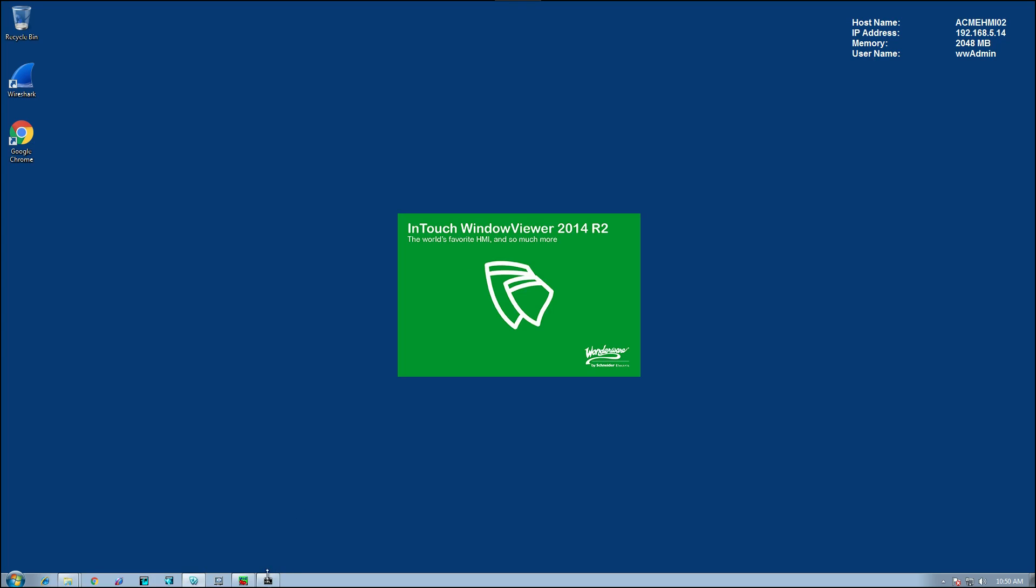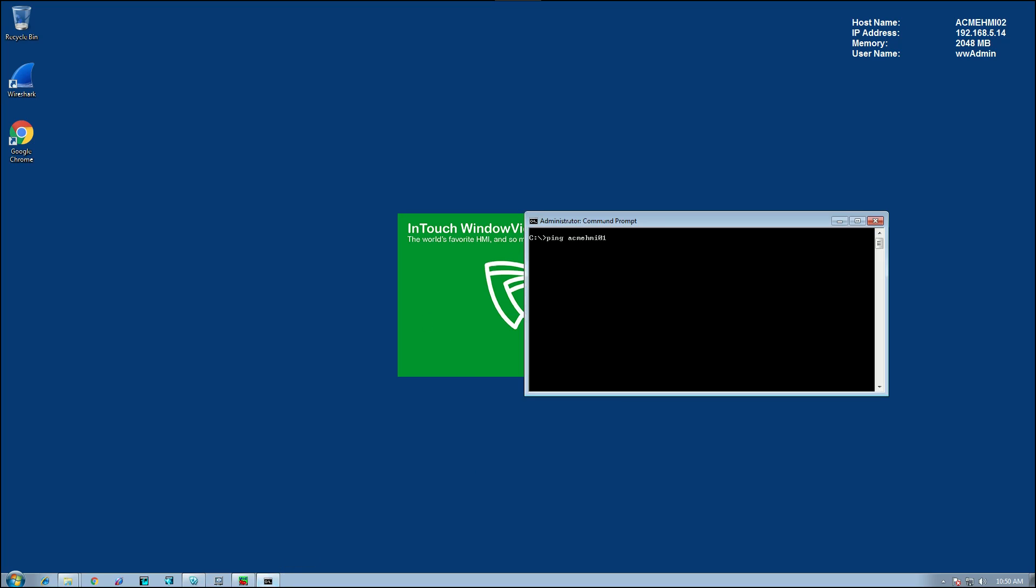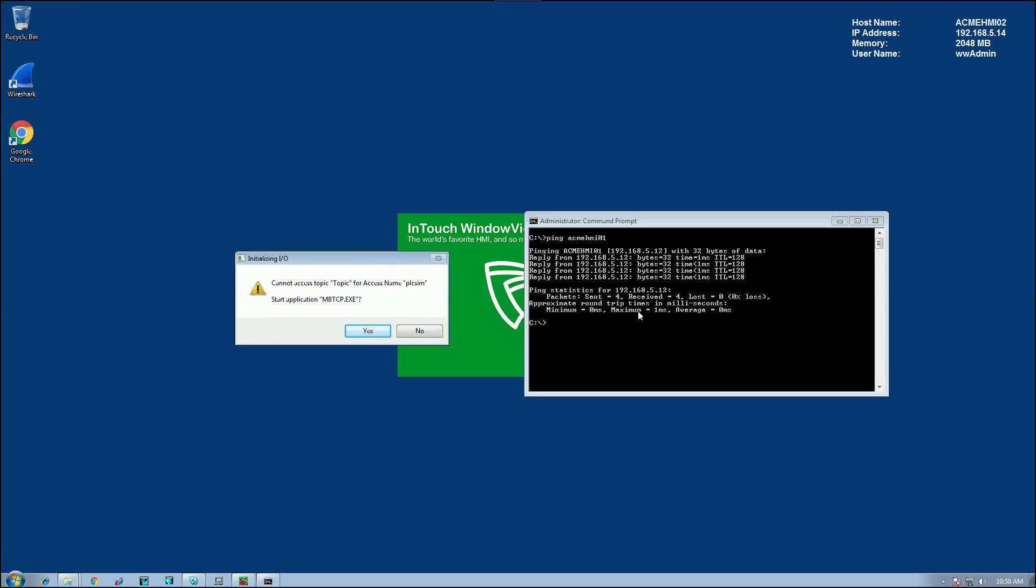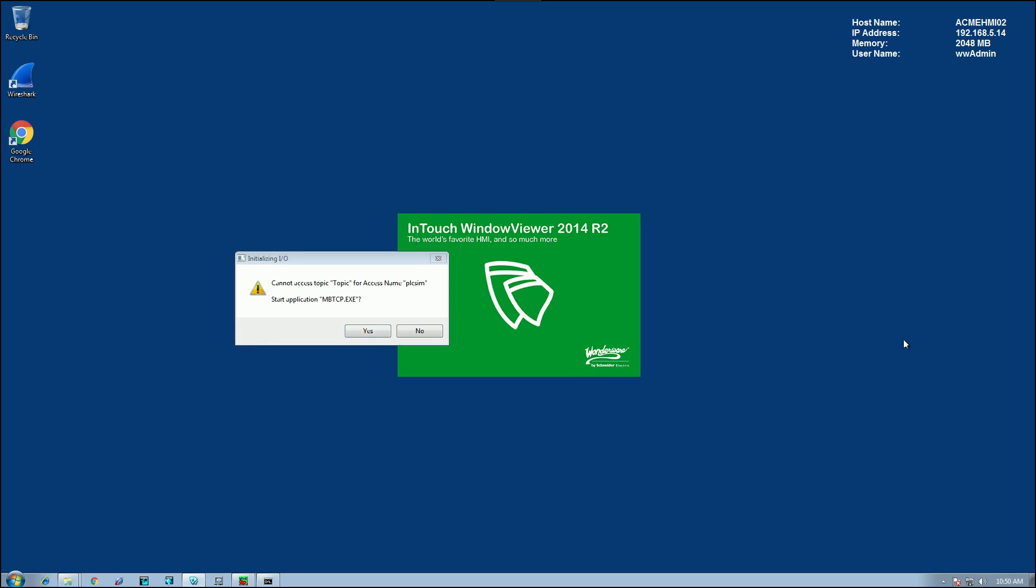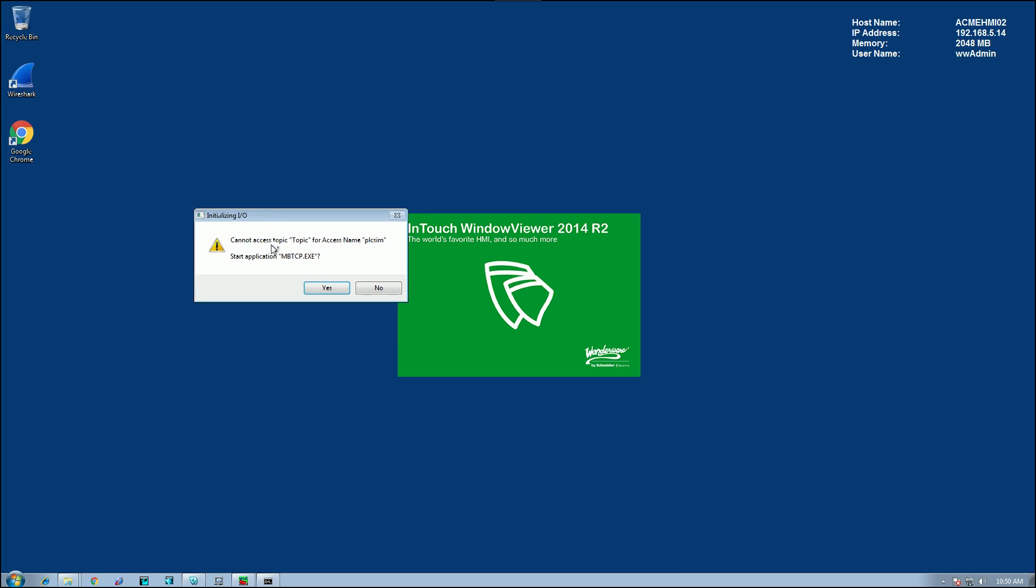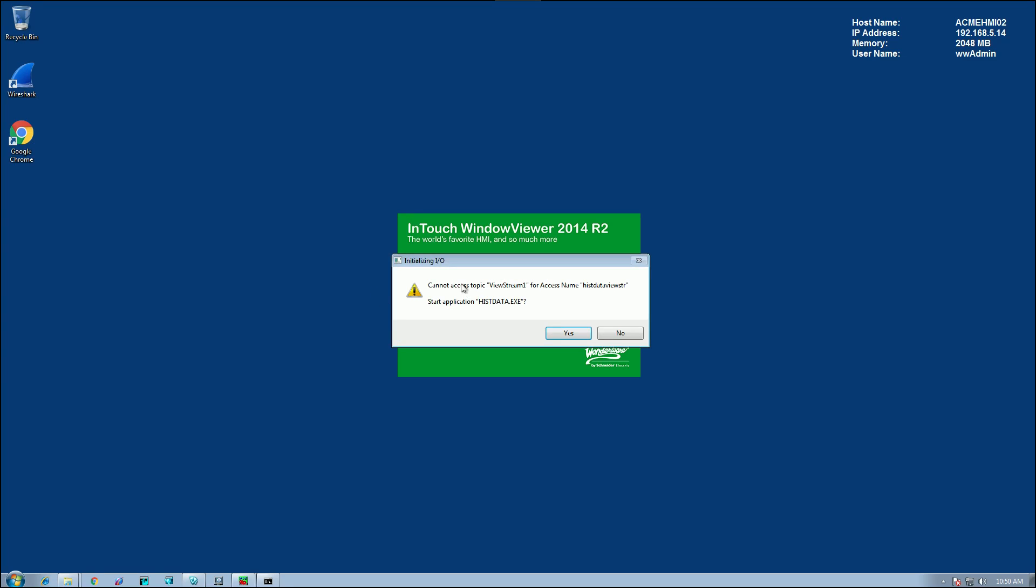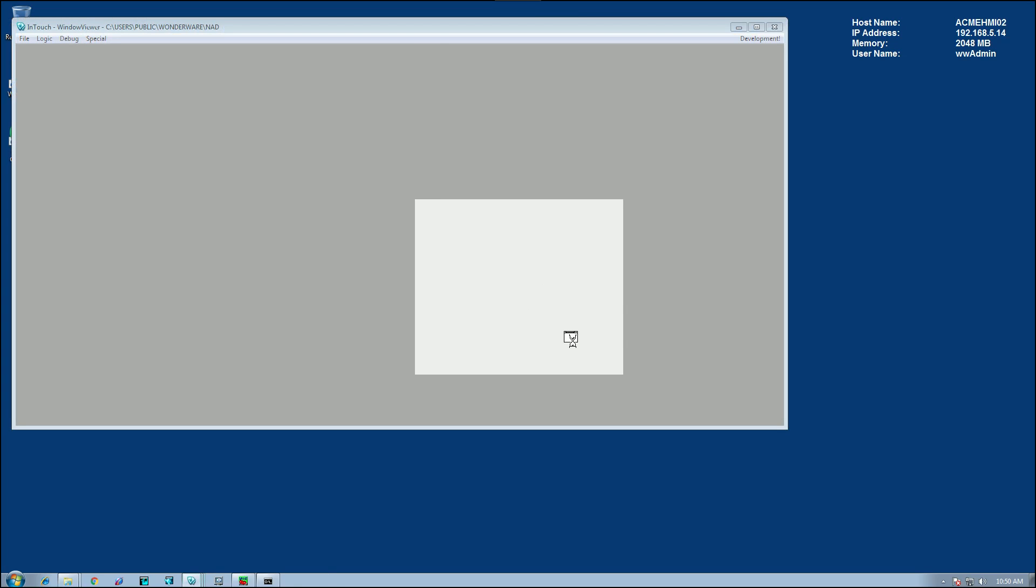Now, prior to doing this, it's also a good idea to ensure that you can actually ping the other node or the master node to make sure there's no network issues. Now, we see in this application here that it wants to start a Modbus TCP.exe IO server. But on this particular node, for demonstration purposes, we don't have that. And so I'm just going to say no. And it wants to start historian. Just simply say yes.